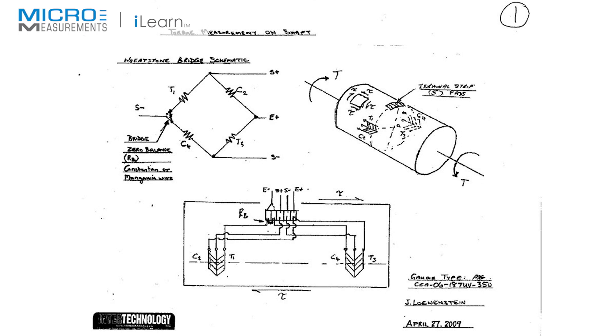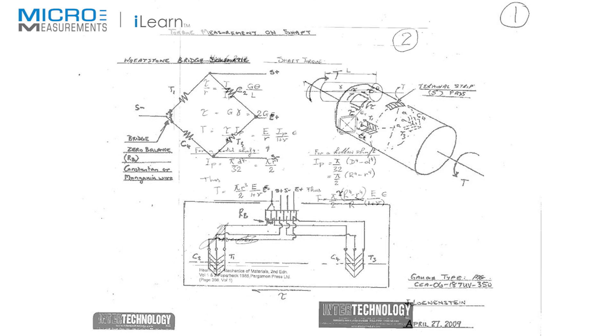I've also drawn a development of the surface of the shaft on the sheet of paper, so one can see the location of the strain gauges, where the tabs of the gauge are, and where the terminals are. We have five terminals on the shaft to connect lead wires between the gauges and the terminals — an extra fifth terminal so that we can complete the corner of the bridge by putting in high resistance wire to balance the bridge if need be. Knowing exactly what you're faced with in the industry, before you even go to site the second time, you have a layout of how the gauges are going to be placed, and when you come to site, you wire it up exactly as drawn on the paper in the developed form.